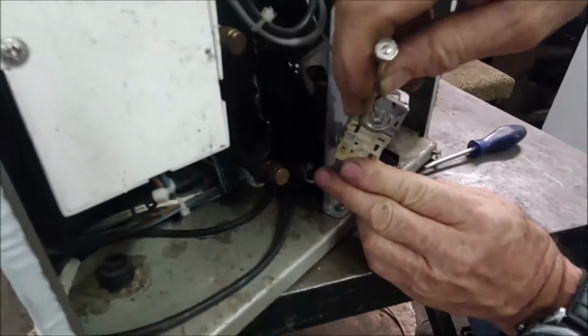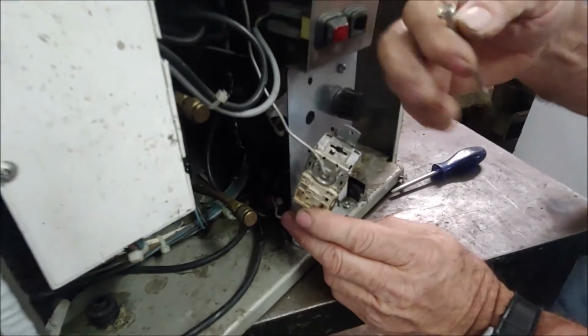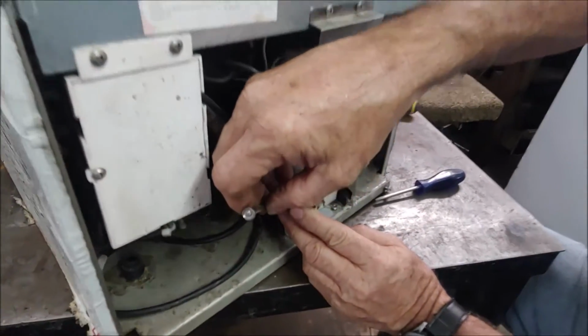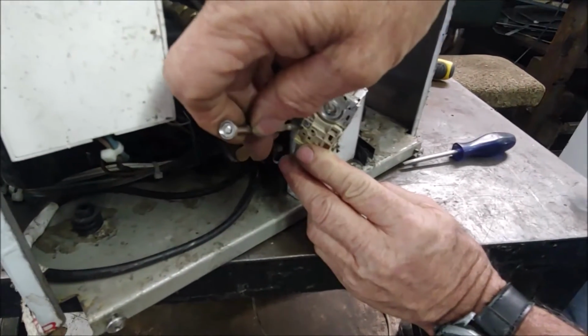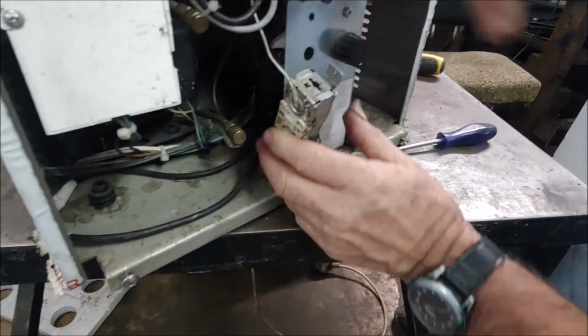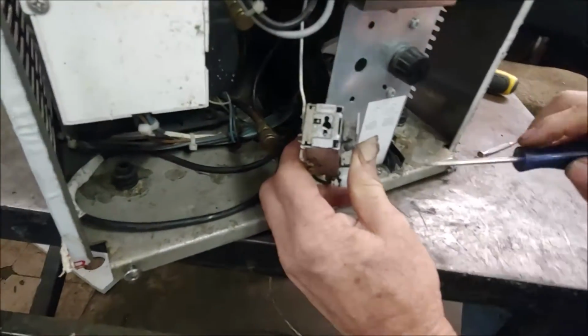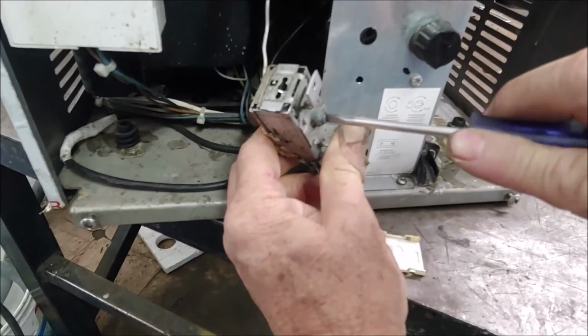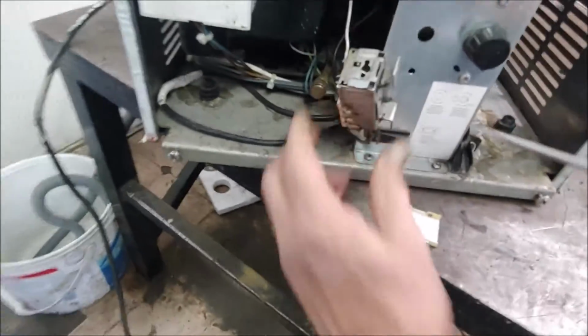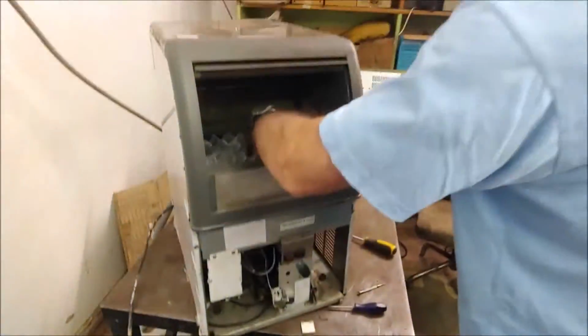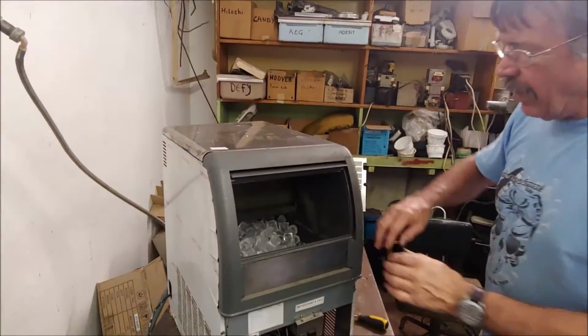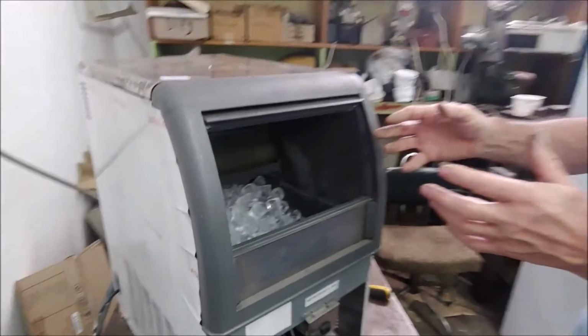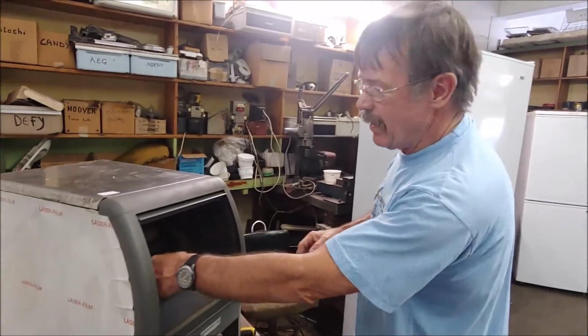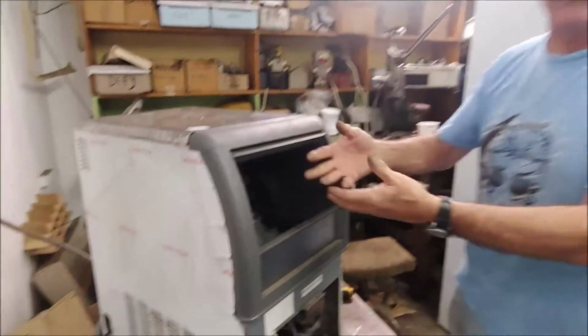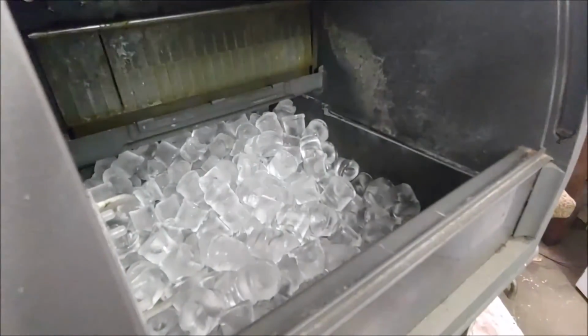But if you turn too much, then the contacts don't work at all. So you must get the differential as short as you can without turning it in too deep. Once you've got it at that position where in the middle of the range you can hear the clicking sound, and it's less than a quarter turn, you leave it there, take the ice cubes off, and within 2 minutes the ice maker will start up and make ice. Once it's made enough ice to cover this probe again, it will switch itself off. And that is how I adjust the thermostat on these Scotsman ice makers.